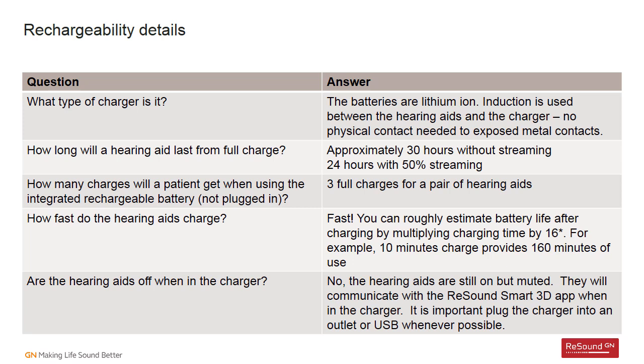Here are some common questions about the ReSound charger. What type of charger is it? The batteries are lithium-ion. Induction is used between the hearing aids and the charger. No physical contact needed to exposed metal contacts. How long will a hearing aid last from full charge? Approximately 30 hours without streaming and 24 hours with 50% streaming. How many charges will a patient get when using the integrated rechargeable battery, meaning it isn't plugged in? The patient will get 3 full charges for a pair of hearing aids.